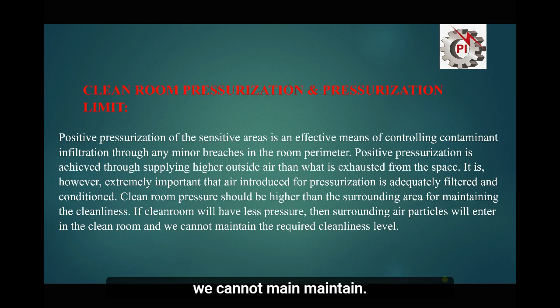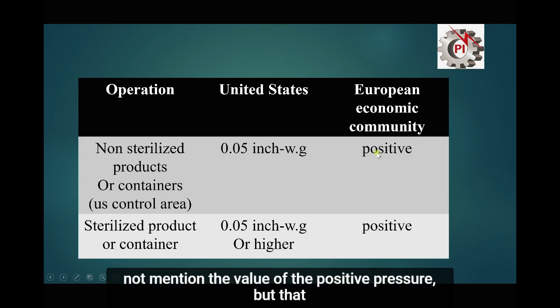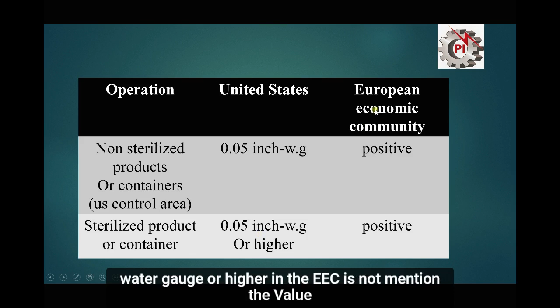We will see this picture. The United States guidelines say that for non-sterilized products, the positive pressure in the clean room should be 0.05 inch of water gauge. For the EEC, European Economic Community, they did not mention the value of the positive pressure, but they say the room should be positive. Same for the sterilized products. The United States guideline says the positive pressure in the clean room should be 0.05 inch water gauge or higher. But the EEC does not mention the value, they just say the clean room should be positive.